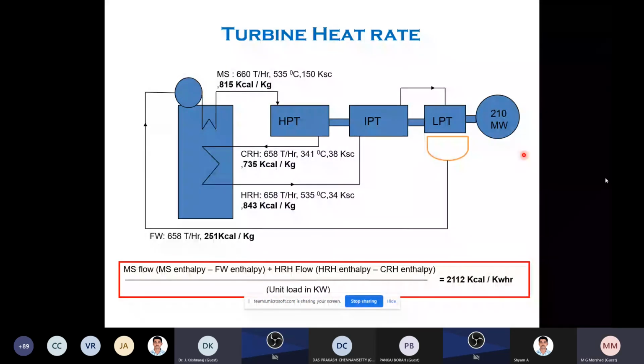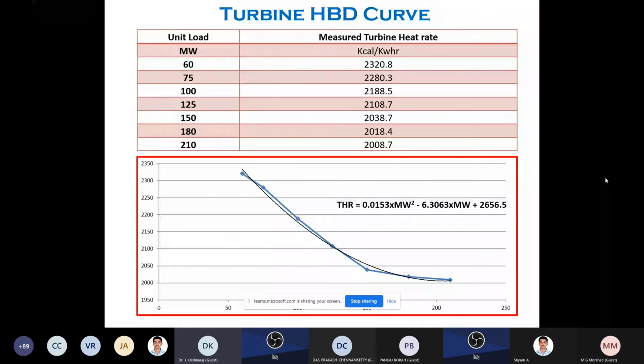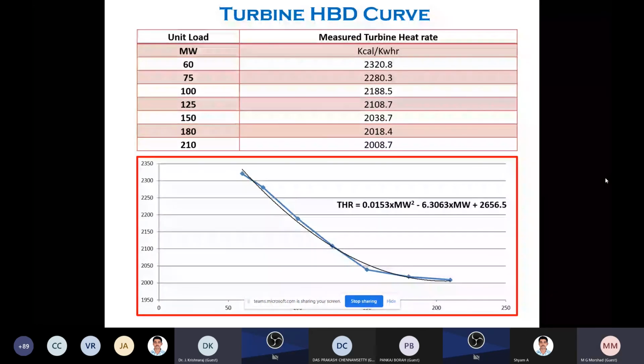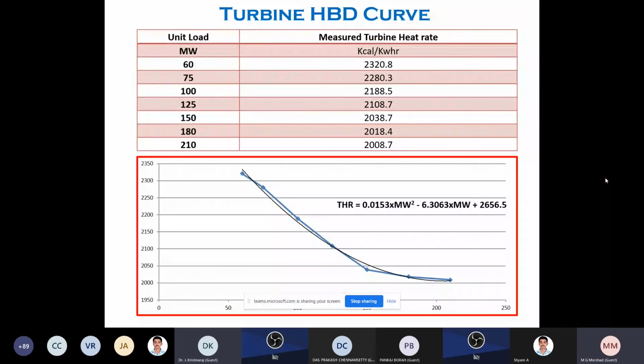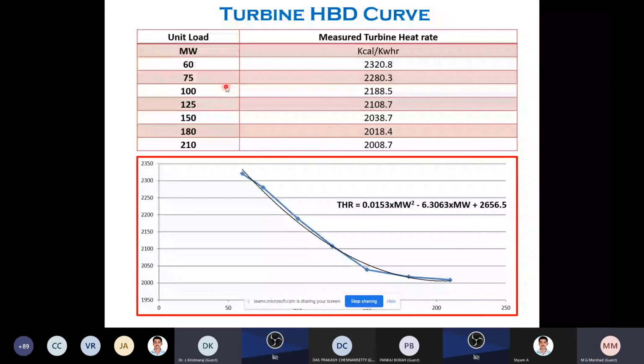Okay. Now, the turbine HBD curve, the heat balance diagram curve, will be given by the manufacturer along with the turbine, because the turbine heat rate will not be the same all the time. It will vary over time; when the load is very low, the heat rate will be high, because it will take more energy to produce the steam.